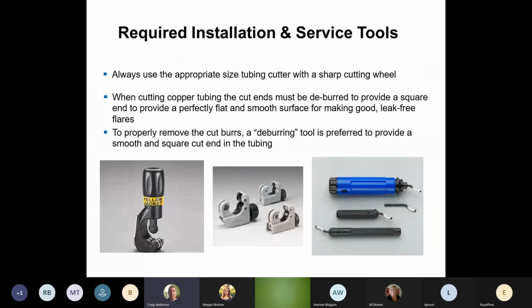Cutting tools, flaring or deburring tools, you don't think it is a big thing, but it does come down to a big thing when we're talking about flaring. A lot of our units now, like mini splits, are coming with flared fittings, so we need to make sure that we have a proper flare. If we're not deburring the copper, then when we're doing our flare, some of the flaring tools will actually make a double flare on the top, and you're not going to get a proper seal.